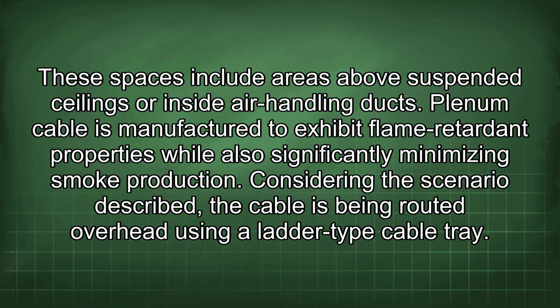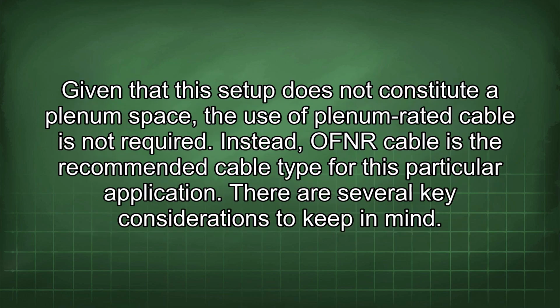Considering the scenario described, the cable is being routed overhead using a ladder-type cable tray. Given that this setup does not constitute a plenum space, the use of plenum-rated cable is not required. Instead, OFNR cable is the recommended cable type for this particular application.